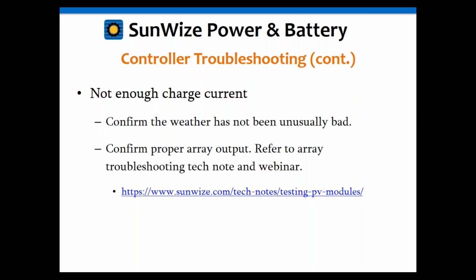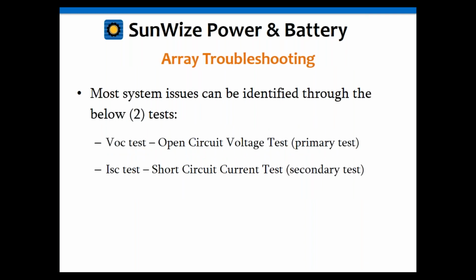Okay, and the other thing is then to confirm that the array is actually putting out what it's supposed to put out. And this is going to bring us back around to the array troubleshooting webinar that I had just done a few weeks ago. So let's go back into the array troubleshooting. Let's just do a quick review of that. There are two basic tests you can do to determine how your array is functioning. One is the open circuit voltage test, and the other one is the short circuit current test.